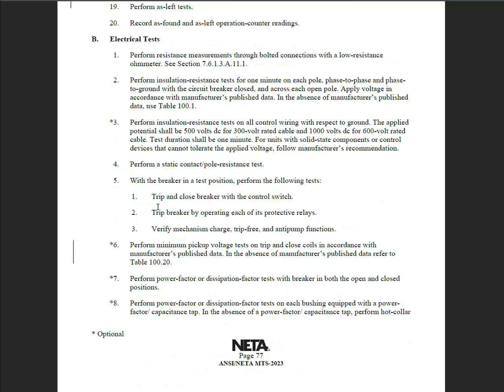Now let's get on to the electrical insulation resistance. All right. In the absence of manufacturers, use table 100.1. Everyone likes to just go straight to that table. You are wrong. You do not go to that table first. You go to the manufacturer's book first, and on these older circuit breakers, a lot of them don't have insulation resistance testing, okay? They have high pot testing. They performed high pot on all of their circuits and not too much meggers, okay?